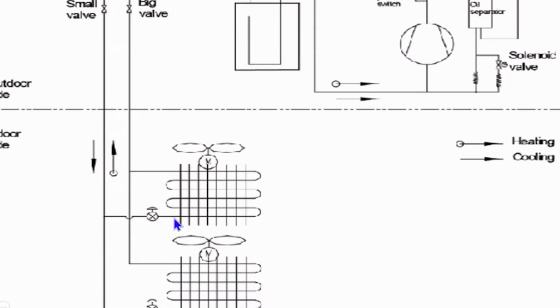But you could also have a restriction in the refrigerant line. You could have a restriction in your piping. Maybe when you bent the pipe, you didn't know it, you kinked it. I don't know, I'm just giving you all scenarios. I'm not throwing the blame on anybody. But if that EEV is wide open and I'm not getting that temperature differential and I'm not getting that flash gas entering that evaporator, then I know that indoor unit's a problem.